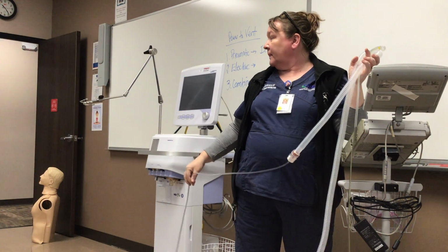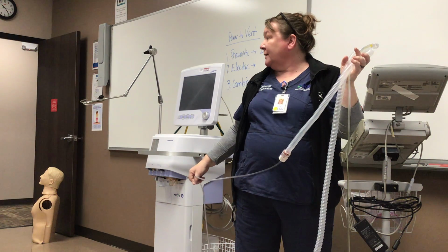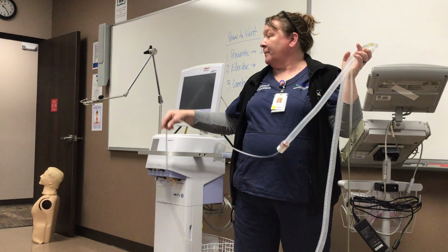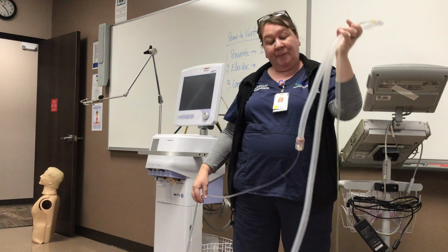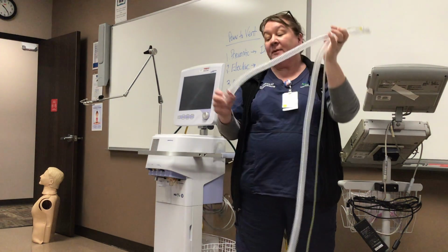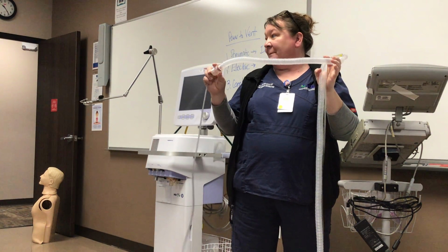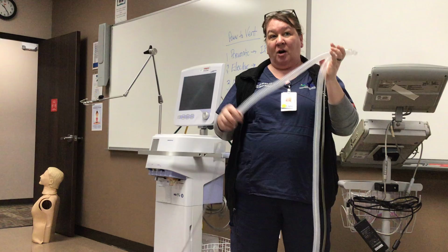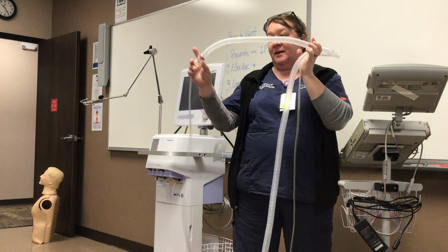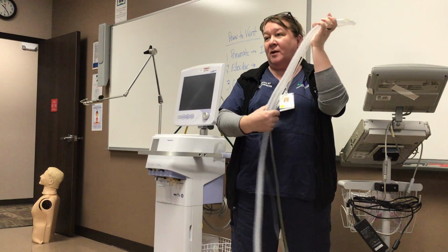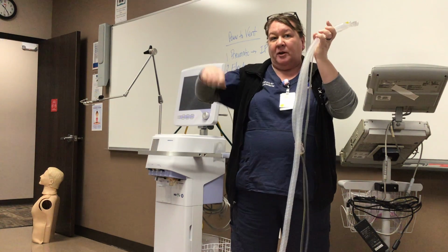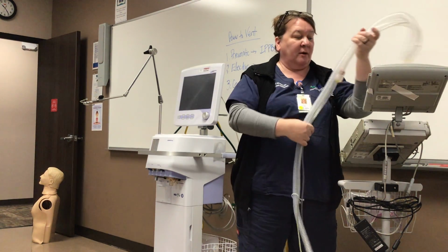So that whole circuit is just replaced? Yes. I was just going to ask, do you put a filter in between? No, it's just replacement. But a problem that we sometimes have is that these get water in them and the valves stick. That's a common problem with LTVs: these valves need to be replaced or dried out. Sometimes you can just take it apart and shake it out, get some excess water out of it.